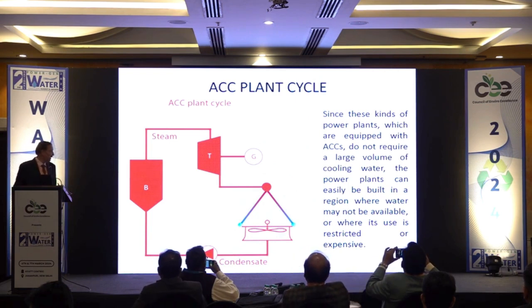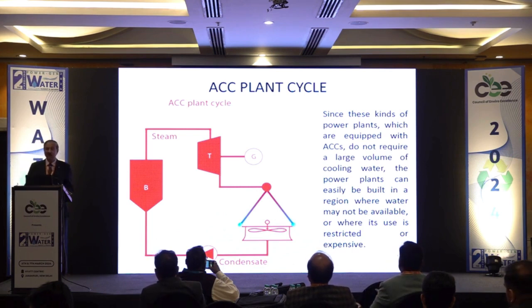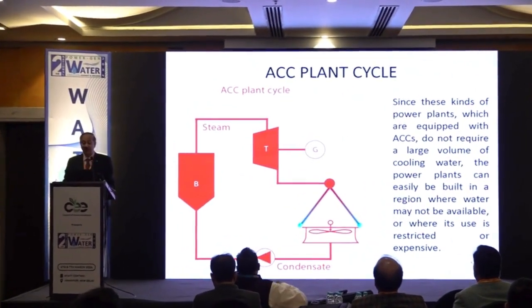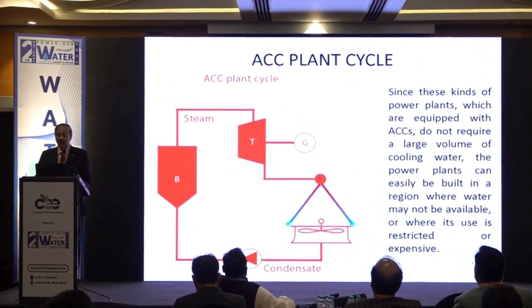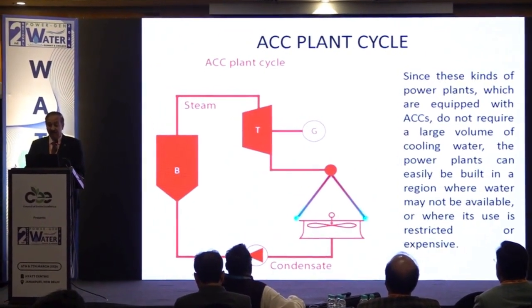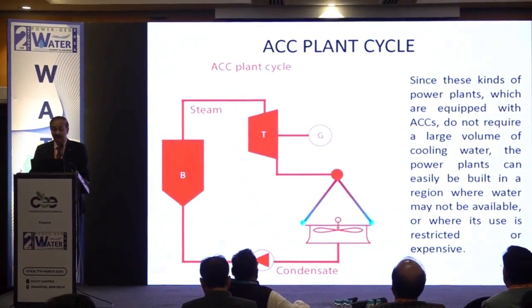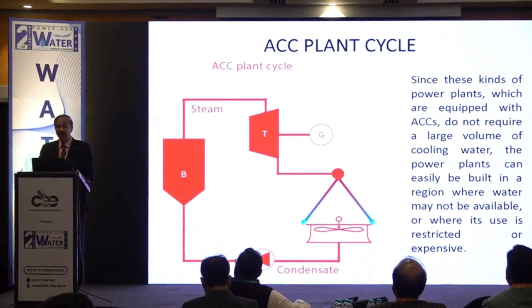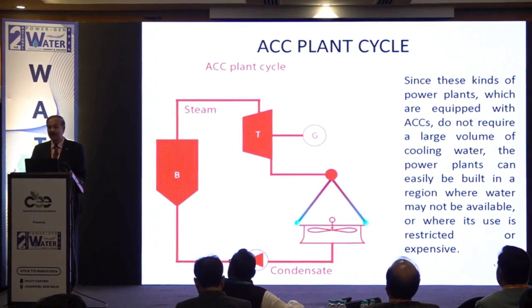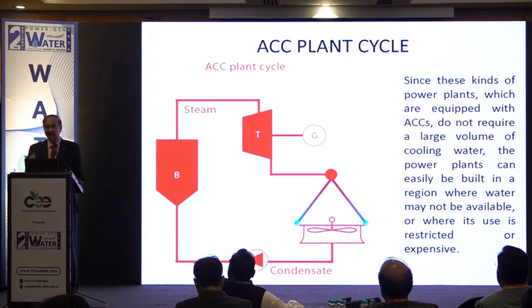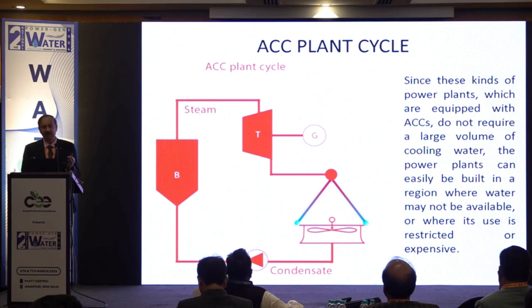there are fans below the ACC plant which help in circulation of the air, ambient air, which causes cooling. These kinds of power plants which are equipped with ACC do not require a large volume of cooling water. The power plants can easily be built in a region where water may not be available or water availability is scarce. So this is basically the crux. That, as one of the earlier speakers told, that we have to take a holistic view of the scenario.